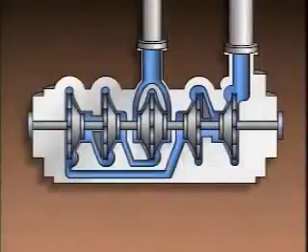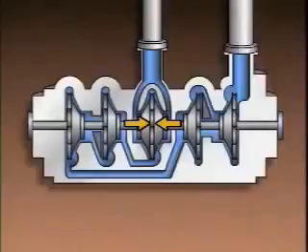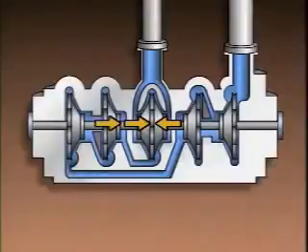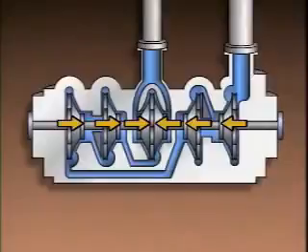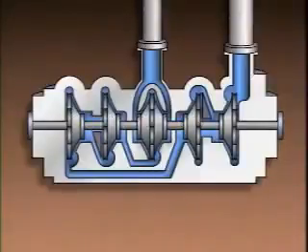On this pump, the arrangement of the impellers is used to offset axial thrust. Processed liquid enters the first stage impeller from both sides, so the pressures on both sides of the impeller are equal. The suction eyes for the second and third stage impellers face in the opposite direction from the suction eyes of the fourth and fifth stage impellers. Since the forces caused by axial thrust are in opposite directions, they tend to cancel each other out, keeping axial thrust to a minimum.